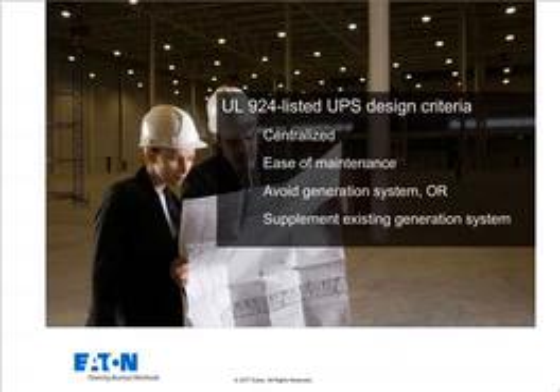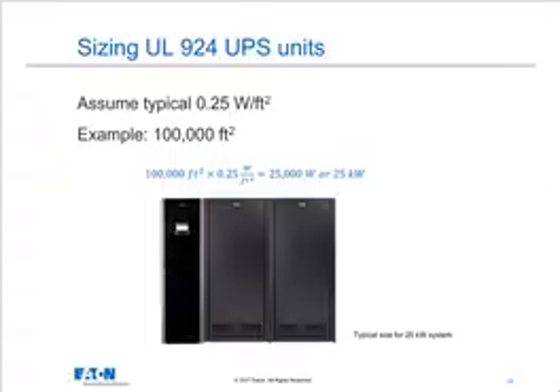Or I can use the UPS to supplement my existing generator, so in this case I would not need a 90-minute battery on the UPS, only a 4 or 5 minute battery while the generator starts and stabilizes. So how do I size a UPS for emergency lighting? Well, the answer to that is wildly varied, as you can imagine. But let's just pick a rule of thumb here so you can get an idea.